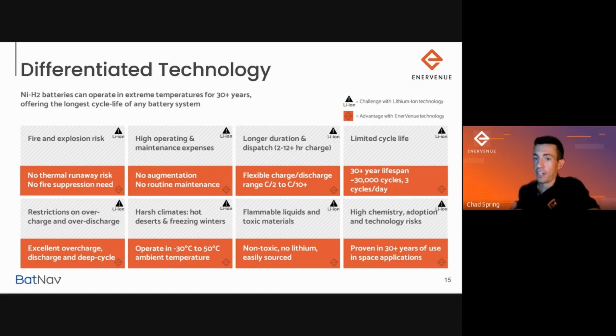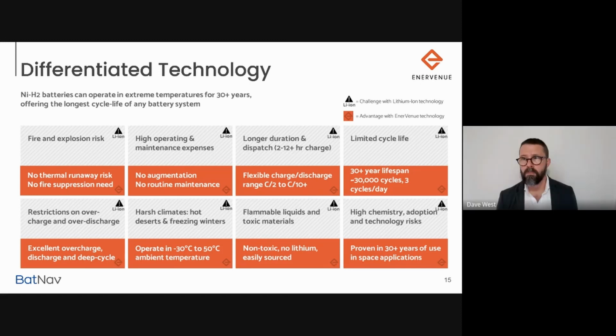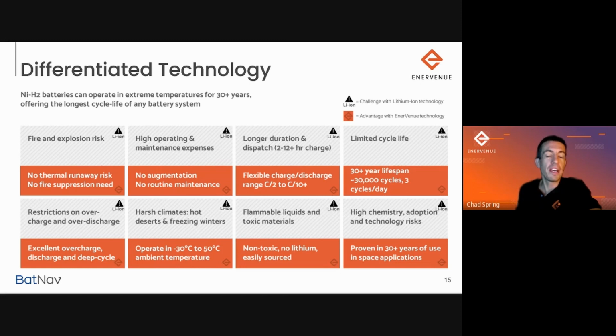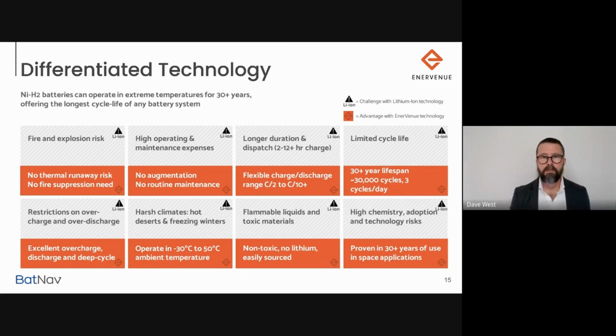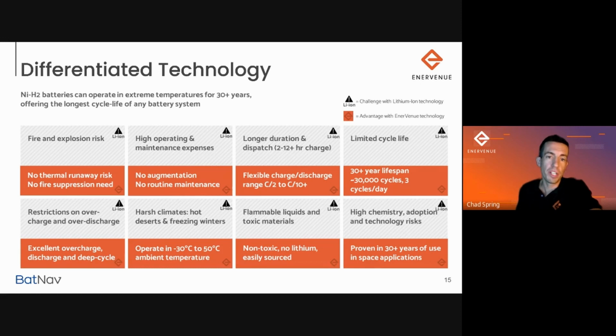We don't have degradation, but lithium-ion, you don't have degradation? Right, so that's typically - lithium-ion is going to typically degrade around 2% per year, and it kind of depends on how frequently you're cycling it. With ours, it's around, depending on how many cycles, anywhere from 0.2 to 0.4% per year. So an order of magnitude less.